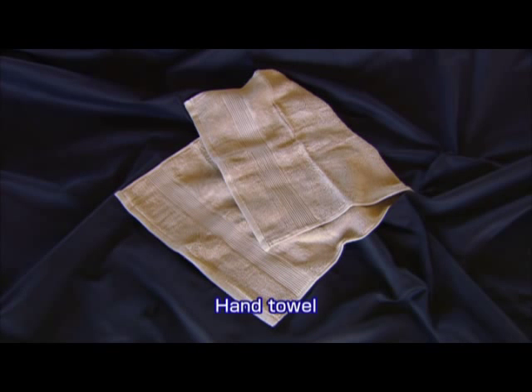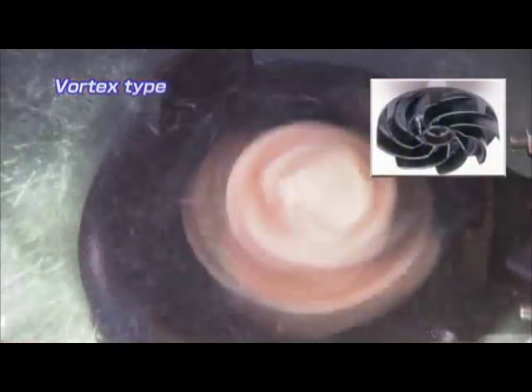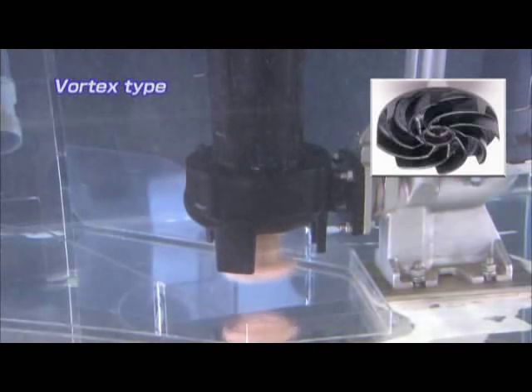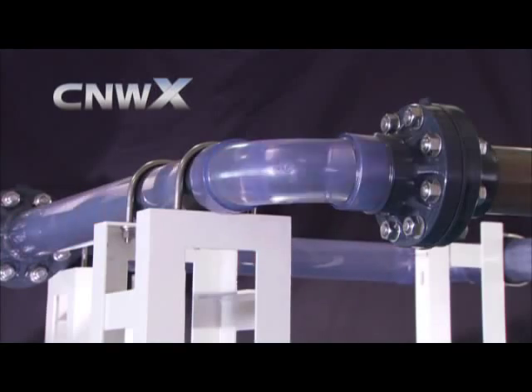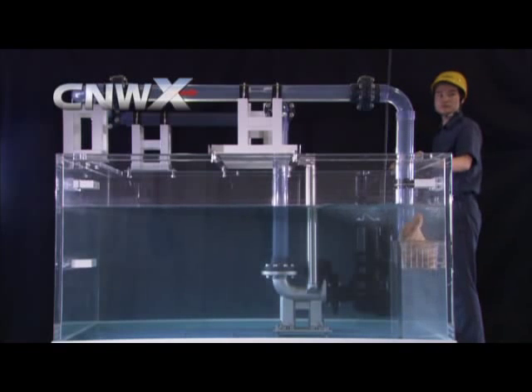First, let's try a towel. Clogging occurs with the conventional vortex-type pump. What do you think will happen in the case of the non-clog scroll submersible pump? As you can see here, even an item such as a towel, which is liable to become entangled, passes through the pump without clogging it.